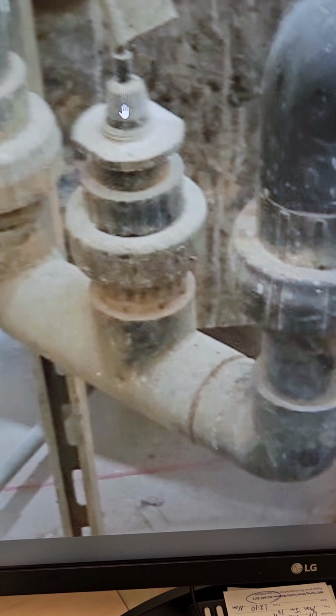So this probe went into a Spears pH trap that we build with a socket union, basically a threaded union, and the probe would thread directly into the end of the union flange. We had a little nipple, and it would go down into the stream. The electrode would get down into the stream. This picture here shows a more modern Hawk probe.